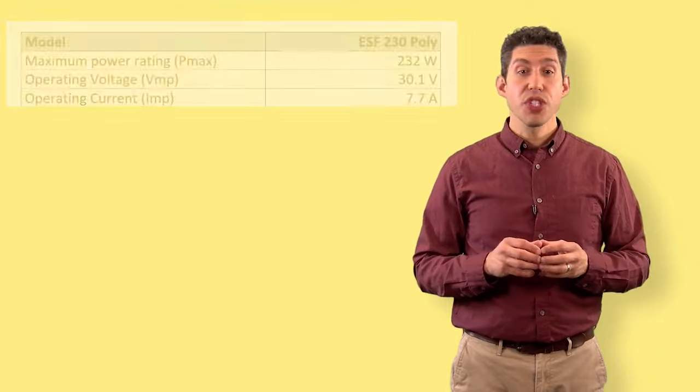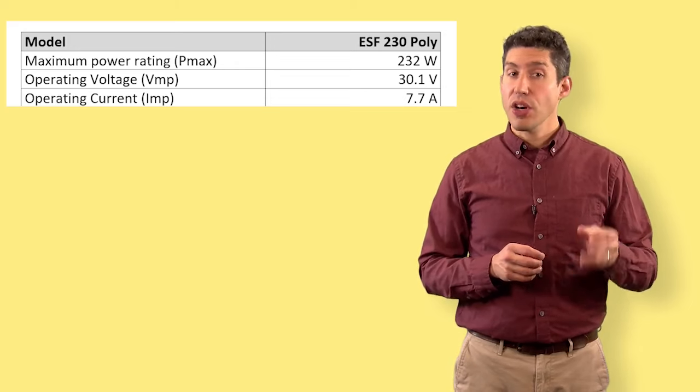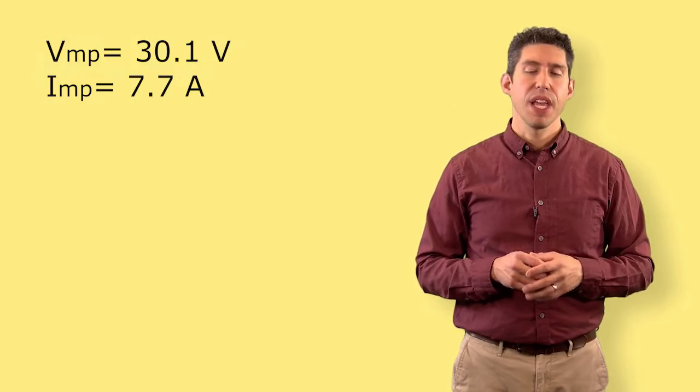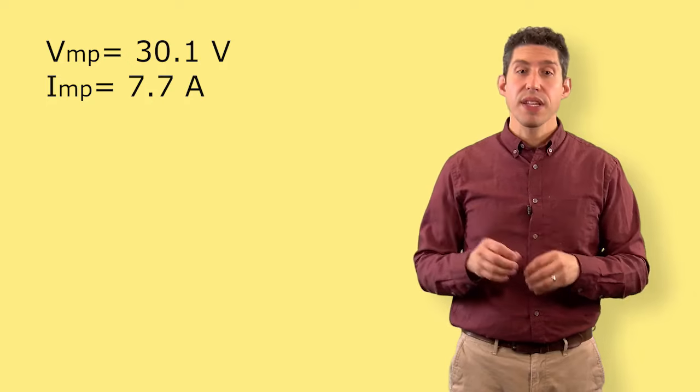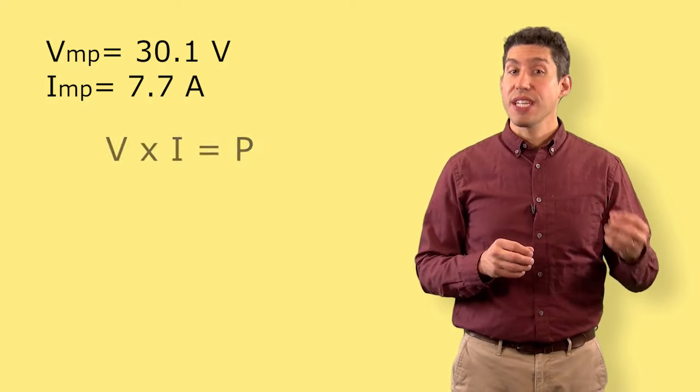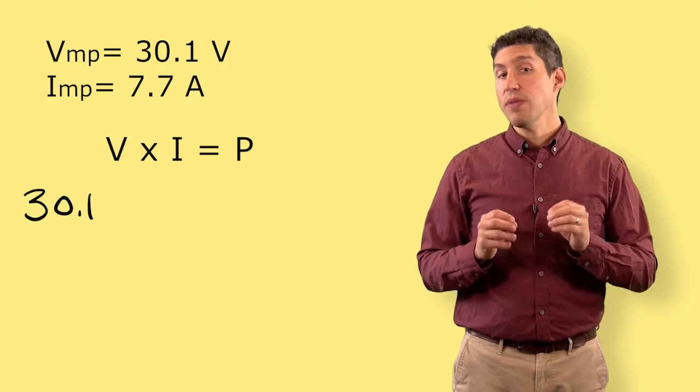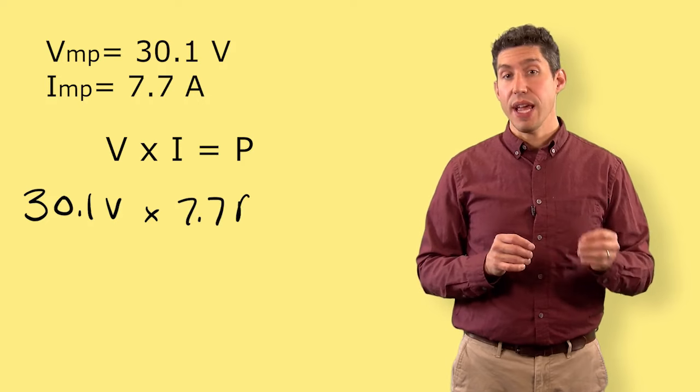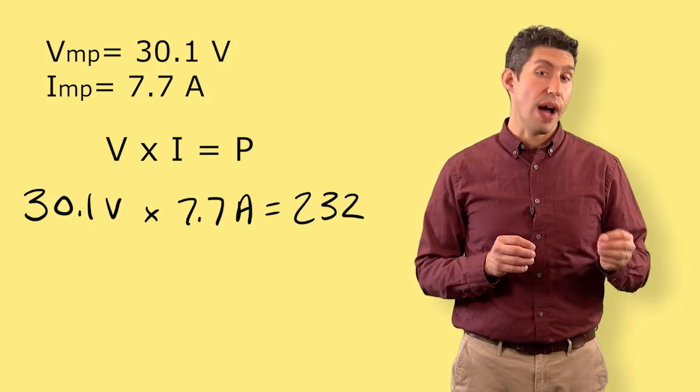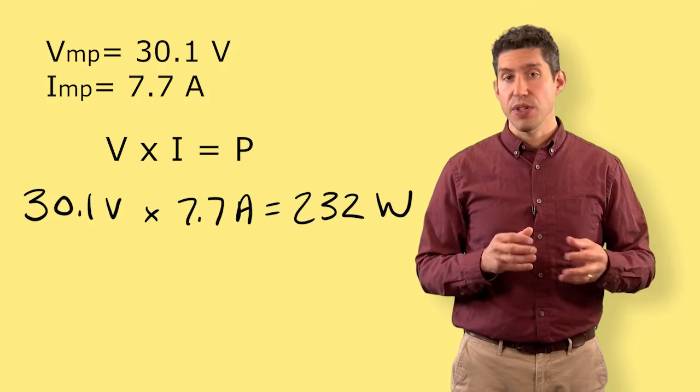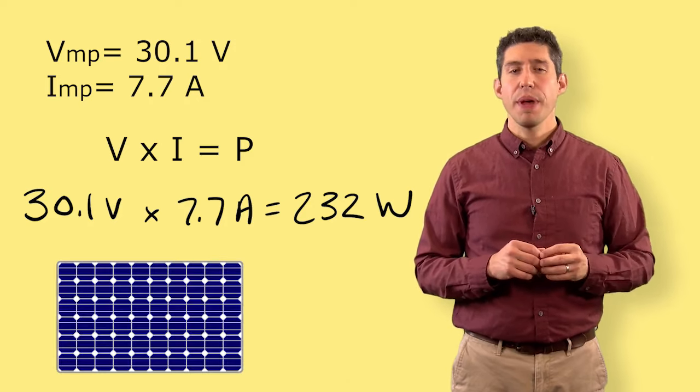I've taken some voltage and current values from a specification sheet. The voltage at maximum power, VMP, and the current at maximum power, IMP. If we want to calculate the maximum power, which is in the units of watts, it's going to be equal to the voltage times the current. So, 30.1 volts multiplied by 7.7 amps is equal to 232 watts, rounding up to the nearest watt. That would be the output wattage of this individual panel, but that needs to be adjusted for standard test conditions.